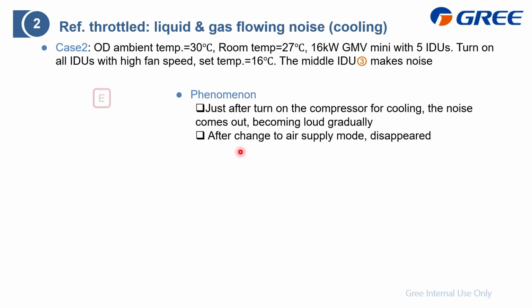Here is another case. It is a 16 kilowatt GMV mini with 5 indoor units. The outdoor ambient is 30 and the indoor room temperature is 27 degrees. This time we will turn on all indoor units with high fan speed and a setting temperature of 16. And we find that from the installation, indoor unit 3, which is in the middle, this one, makes noise. And here is the phenomenon. Let's hear the noise. Just like this.